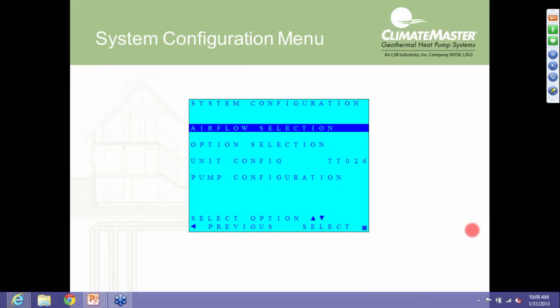All right, the first thing we're going to go into is system configuration. And system configuration, this menu is also in the thermostat as well as the service tool. Now, when you get one of these communicating products from Climate Master, again, they are already configured with factory defaults from the factory. So again, under most cases, you're not going to have to go in here and make any changes, unless, for an item like this first one highlighted, airflow, we want to make an adjustment to the factory default airflow settings.